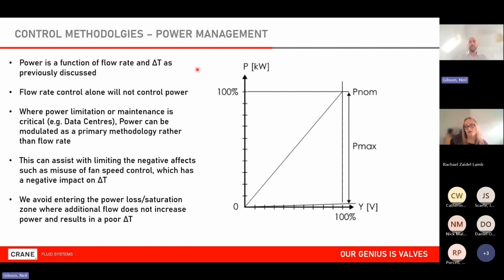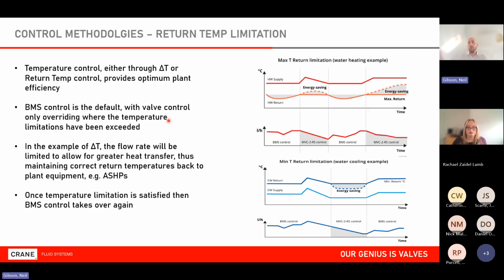But now, if I have delta T as a factor, as a value, if I have delta T and flow rate, I can have power. So now I can drive based on power. Let's say my device has a power output of 5 kilowatts. Let's just pick a number. I can now drive a 0 to 100% control signal based on a target of 5 kilowatts, which means it's constantly compensating flow rate and delta T to achieve that power. So if there is an issue with delta T, it will compensate by delivering a higher flow rate to give me my nominal power output. But we can go one step better than that. We can actually say, if I maintain my return temperature, then I can maintain my power and I can protect my plant at the same time.